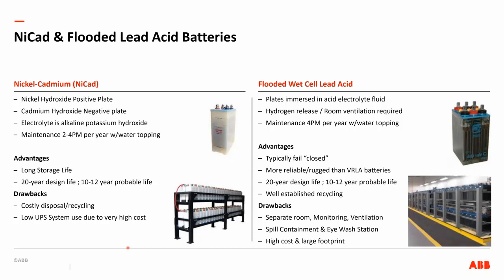But the reason customers like them is that the failure mode of a cell in a wet cell battery is typically a shorted cell. In a UPS battery, where you typically in the US have 240 cells in series, the weakest link in the chain will break the chain. But if it's a wet cell battery and a cell fails and shorts out, then instead of having 240, you now have 239 cells in the string, and the UPS can still operate with that. But of course, that cell needs to be replaced.